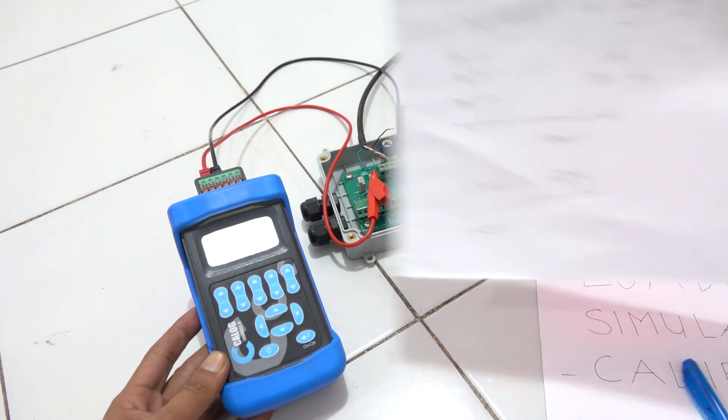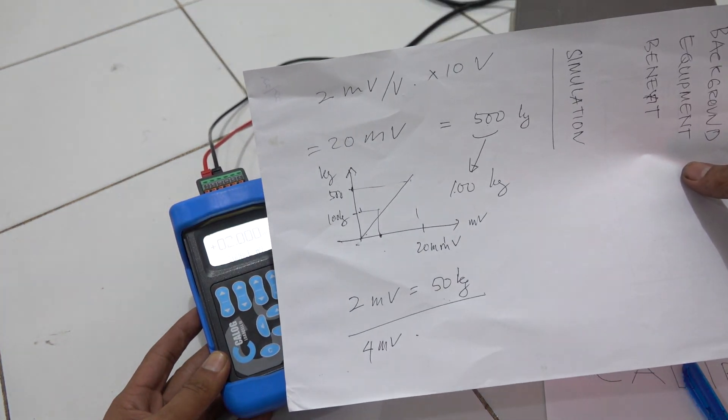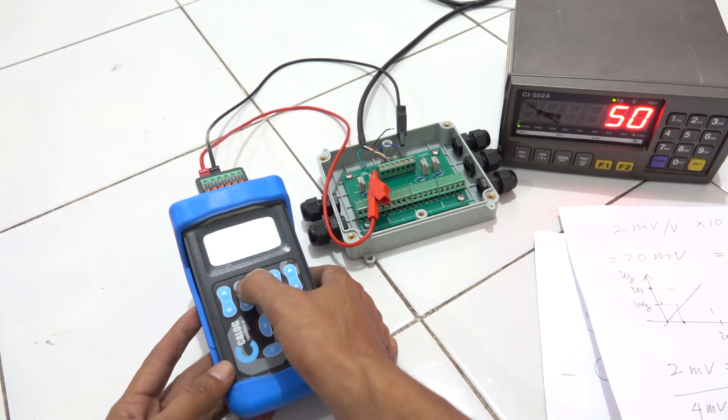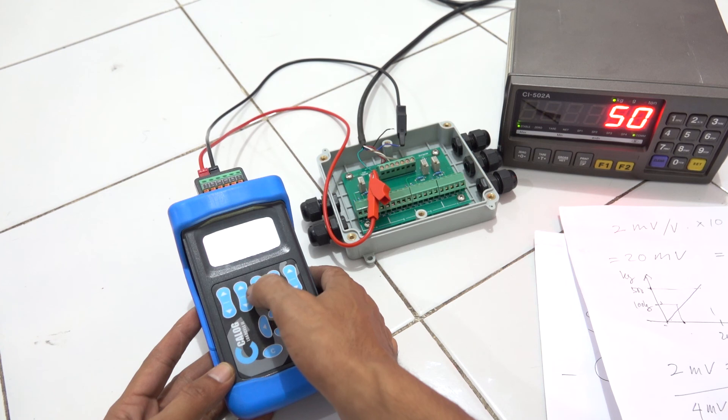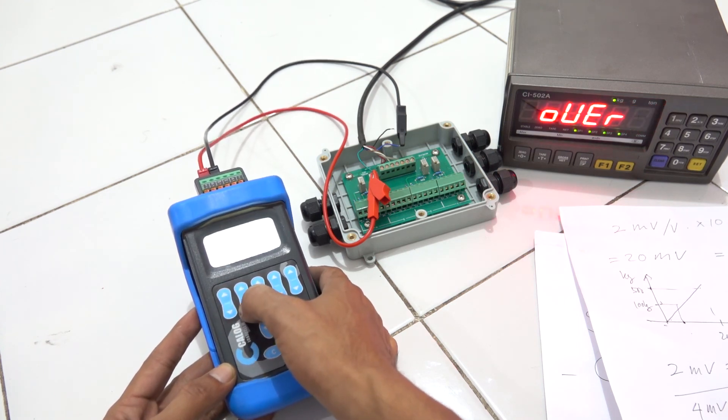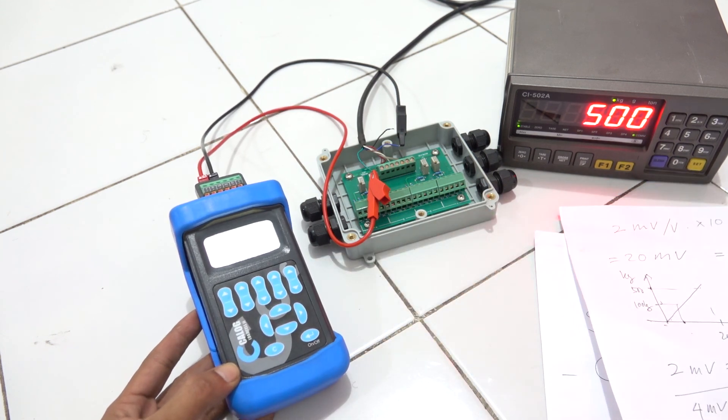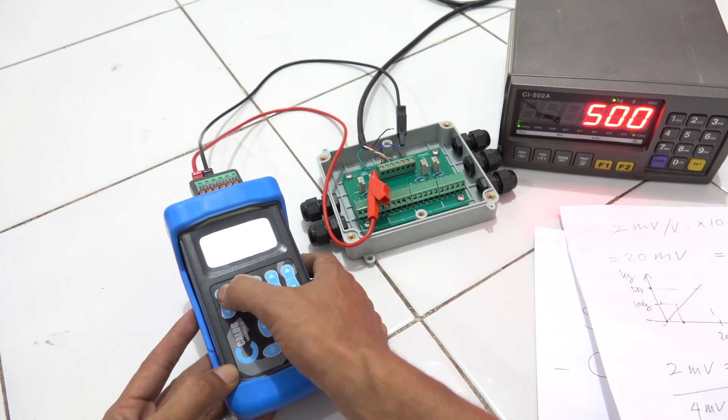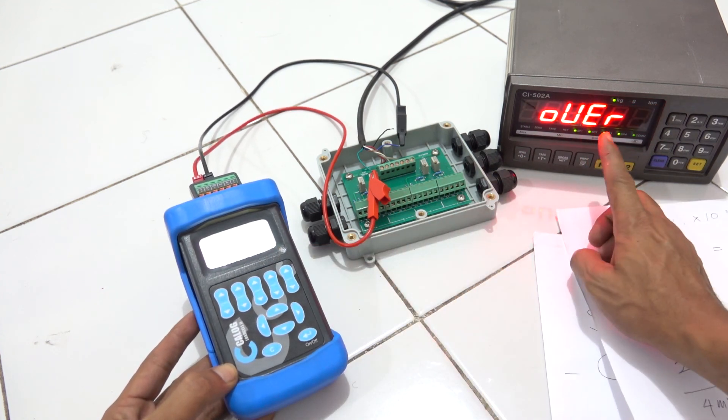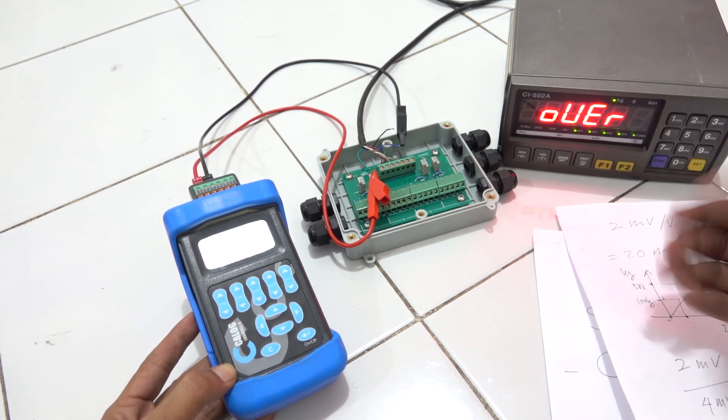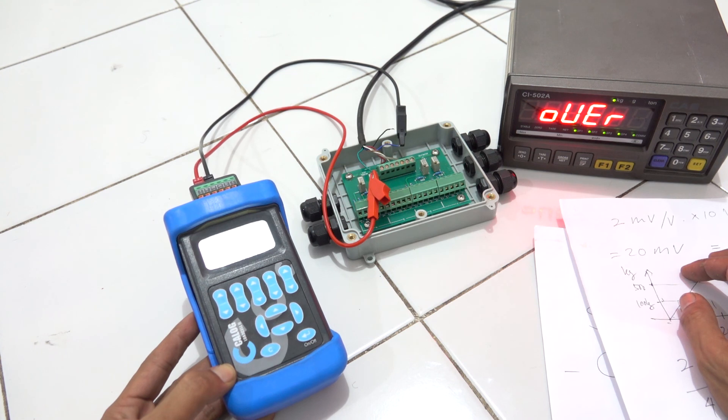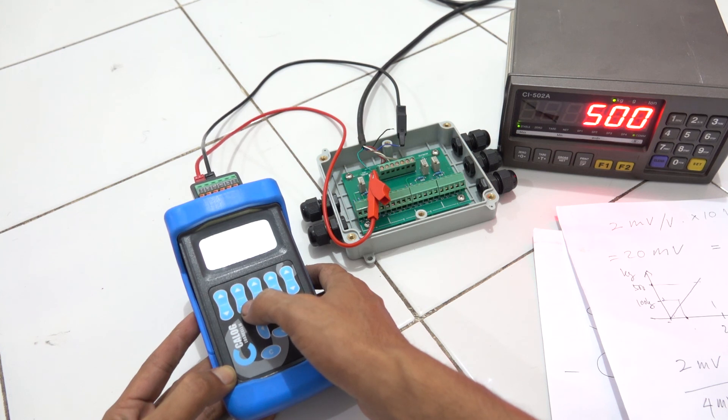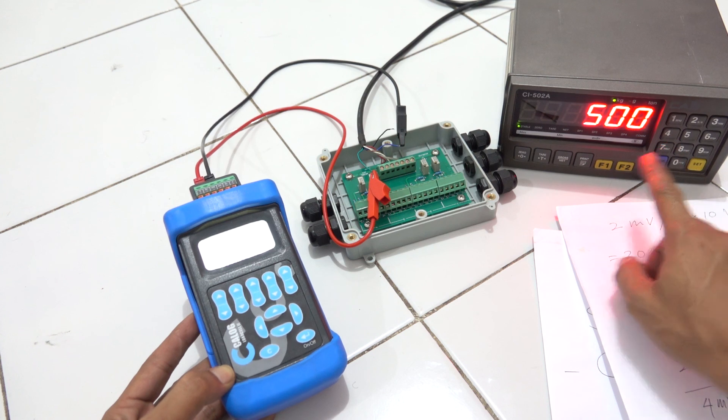See, 2 millivolt will be 50 kg. How about 20 millivolt? 500 kg. But if more than that, let's say 30, there is error. You can see in the user manual what the meaning of this error is, but we can guess right now that the error meaning maybe is overload. So 20 millivolt is similar with 500 kg.